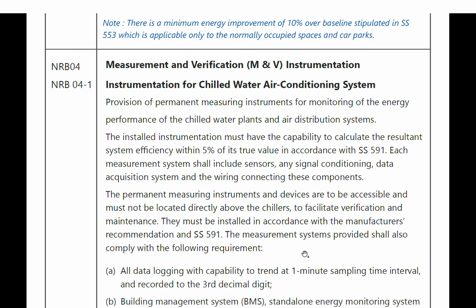Measurement and verification instrumentation will be a part of the instrumentation in chilled water conditioning. Permanent measuring instruments for the energy performance will be part of the chiller plant, as you may have seen in your practical 1, right? You recorded some of the measurements, and in practical 2 you actually took readings from the BMS systems. All these enable you to calculate the resultant system efficiency. So that's how we try to comply with the code for energy efficiency.